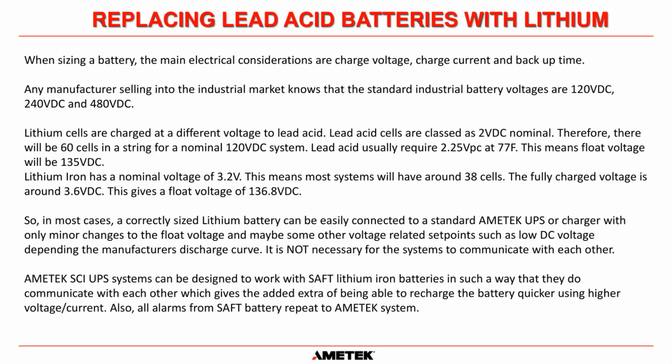So a very long answer, but the short form answer is, if your lead acid battery is getting to the end of its life and you are interested in replacing it with a lithium battery, near enough all the lithium manufacturers have designed their systems so you can plug and play. You can tell them that you want to replace a 120 volt nominal ampere hour lead acid battery that has 3 hours backup time with a lithium battery. They will size that for you, and you can just plug the positive and negative cables into our UPS and it will work without any issues whatsoever.